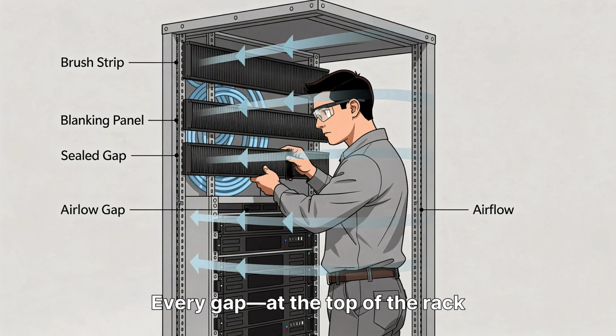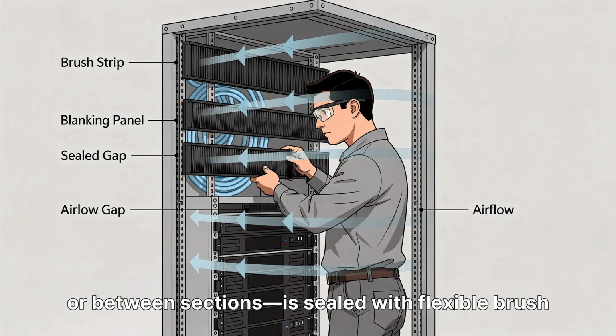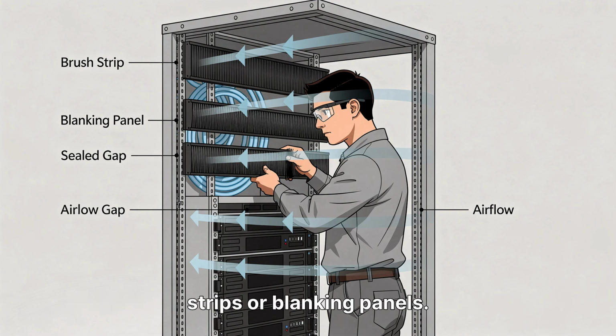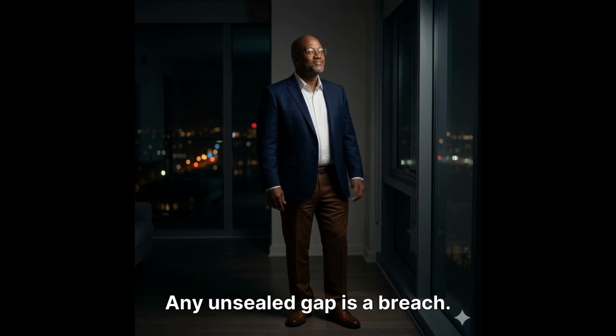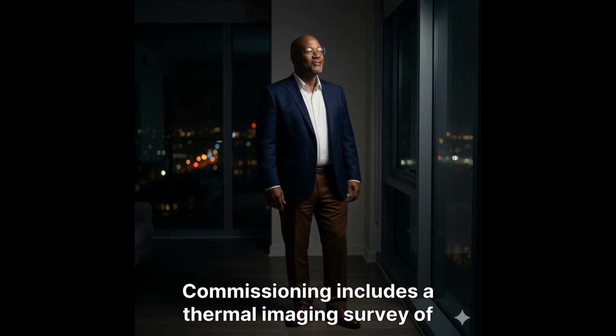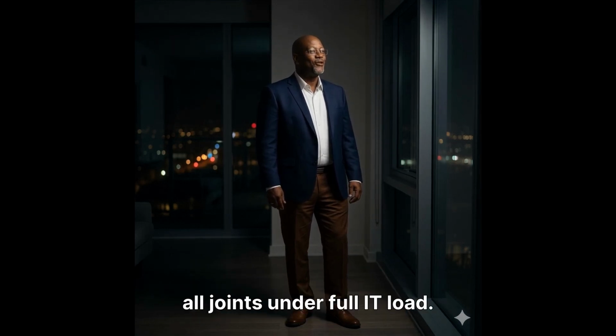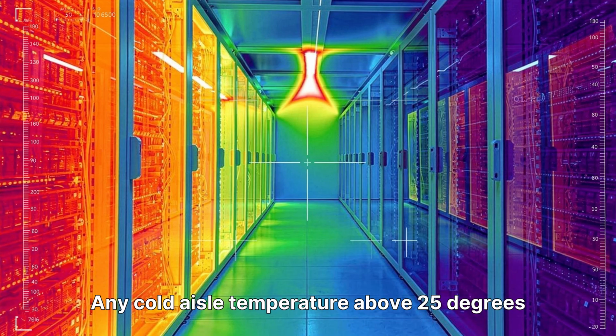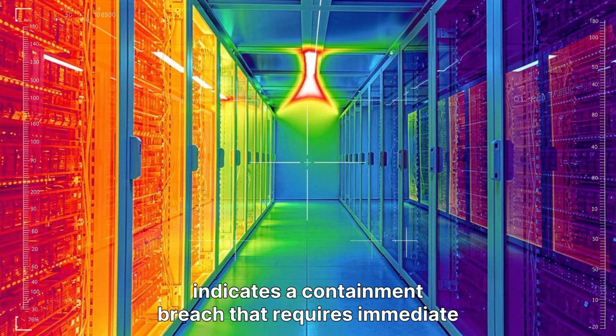Every gap at the top of the rack or between sections is sealed with flexible brush strips or blanking panels. Any unsealed gap is a breach. Commissioning includes a thermal imaging survey of all joints under full IT load. Any cold aisle temperature above 25 degrees indicates a containment breach that requires immediate correction.